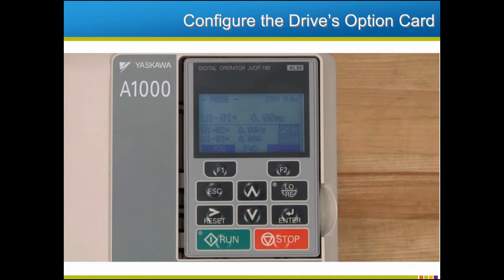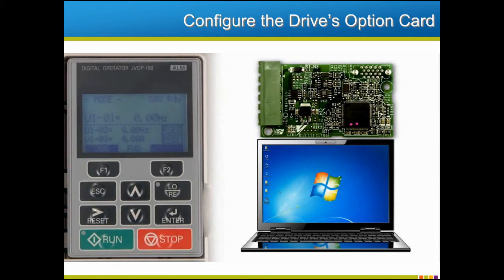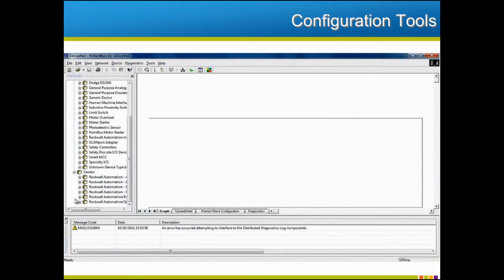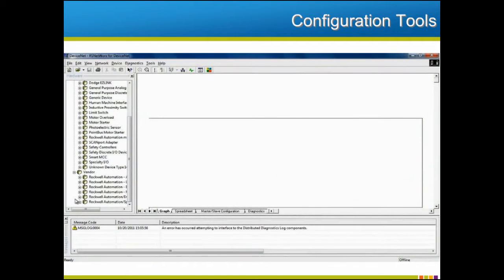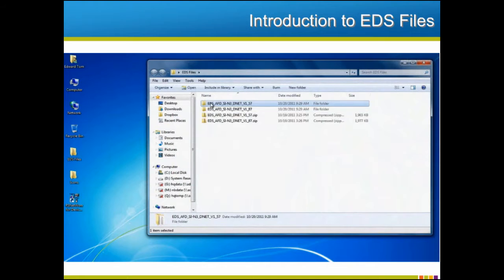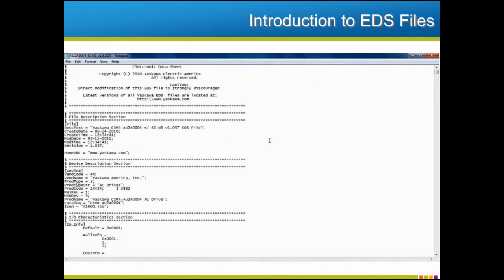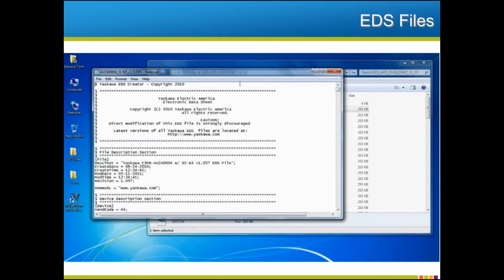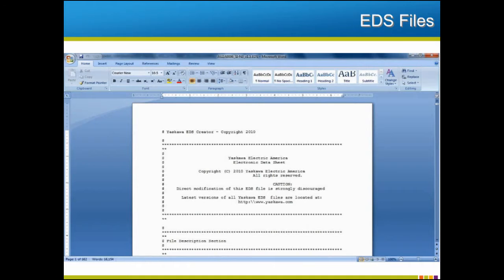Now that the drive is connected to the network, we will need to configure the drive's option card and network to work together properly. To do this, we will need a configuration tool — a software program run on a computer connected to the network that can be used to program the devices on the network. Configuration tools are available from a variety of software vendors, including Rockwell and Omron. Since RSNetWorx from Rockwell Automation is the most common configuration tool, especially in the United States, we will use it in the examples that follow. In this example, we'll configure the drive and network using electronic data sheets, otherwise known as EDS files. An EDS file is merely a text file that contains all the appropriate information about a device, and can be opened and modified with Microsoft Notepad, WordPad, or any other standard text editor.